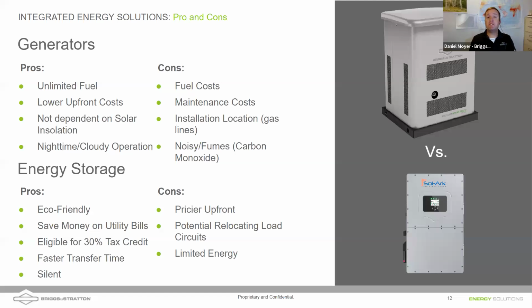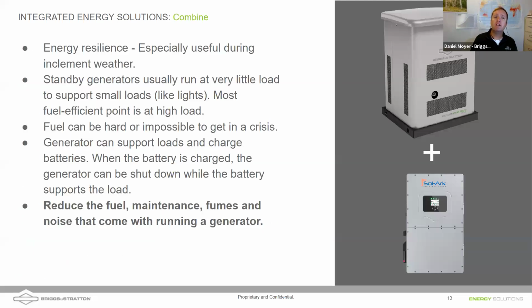That brings me to one of the historical cons of energy storage—having to relocate loads. With the Sol-Ark 15K that John just mentioned, we can take 200 amps, your typical residential service, from the grid into the Sol-Ark, and then come right back out and back up an entire home's panel. So you're not having to relocate those loads. There are some considerations though—if we wanted to do a partial home backup, we would with some of the smaller models, and if you have a meter main, which is common here in California, there may need to be some relocation of loads.